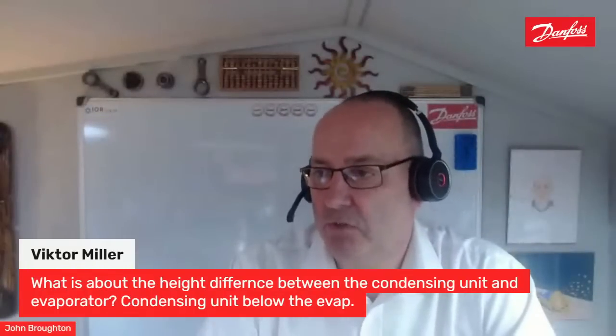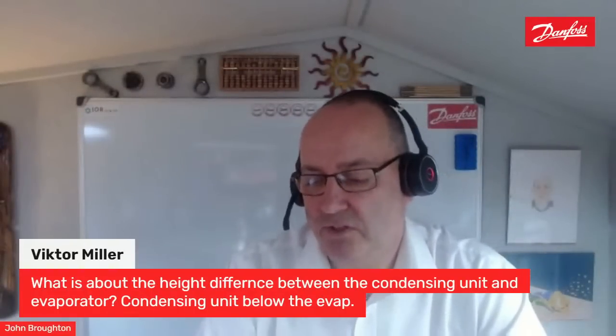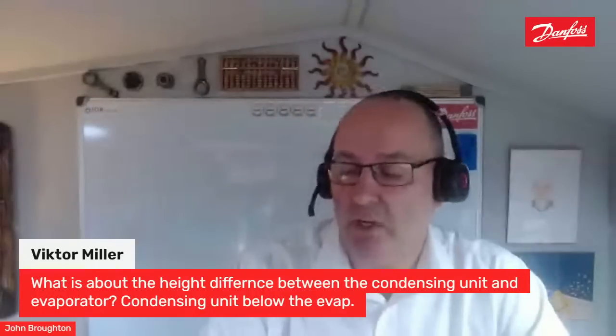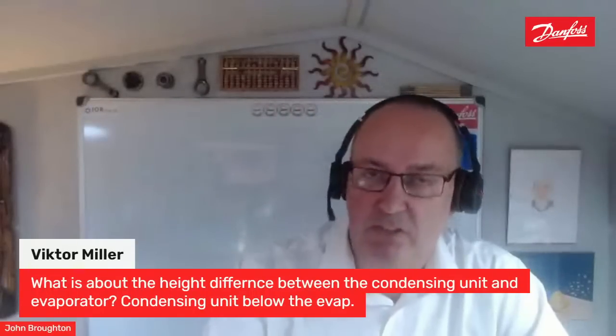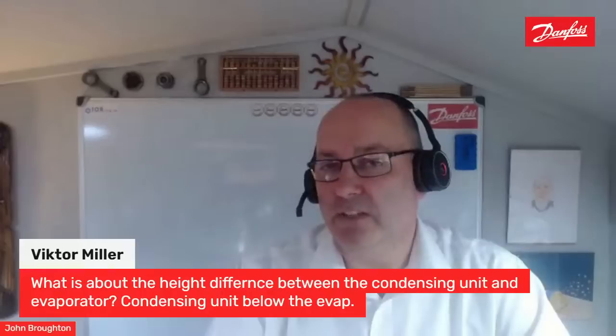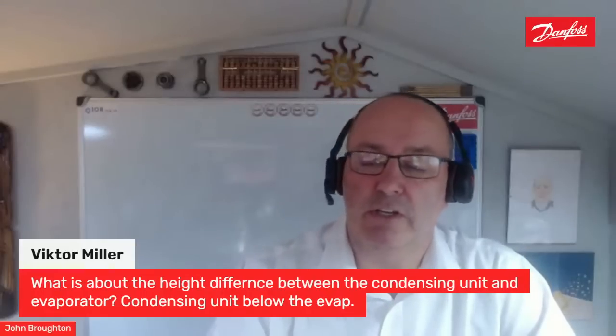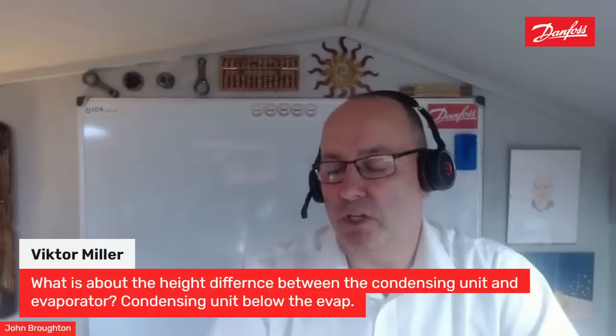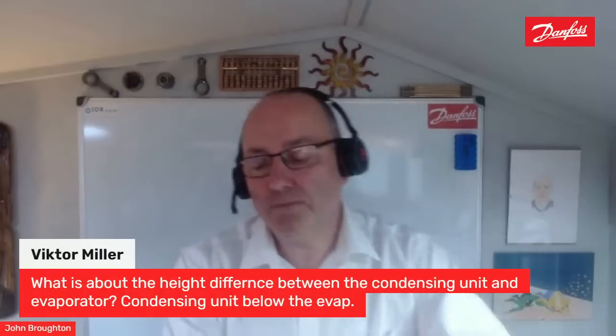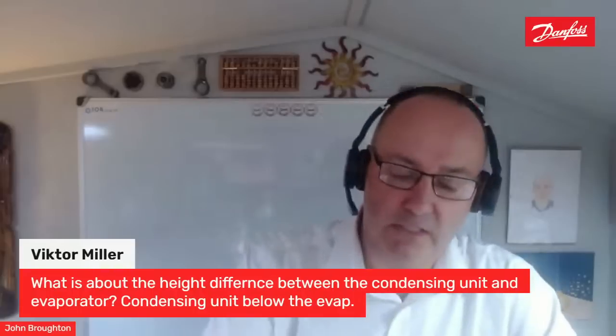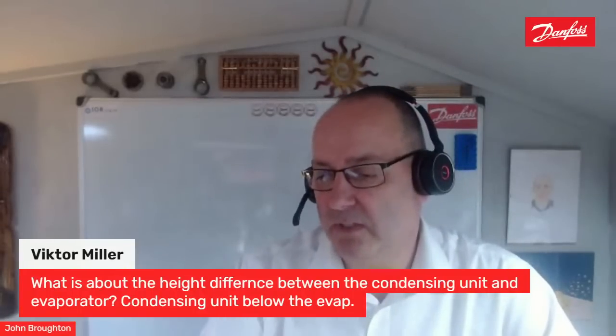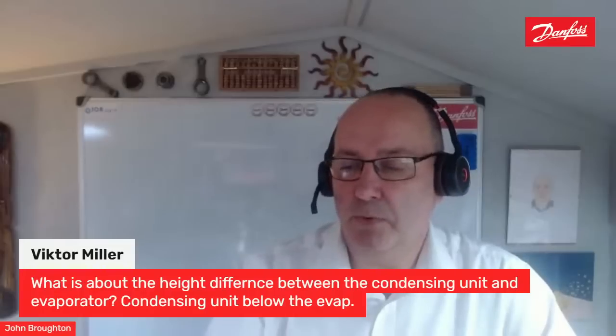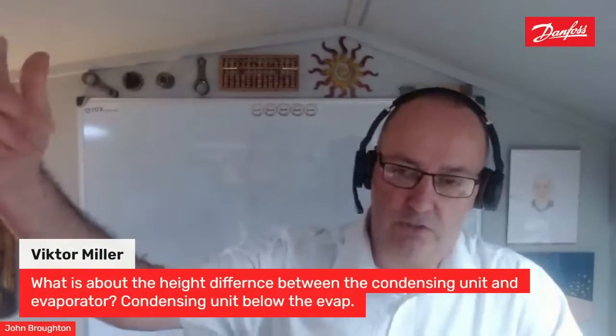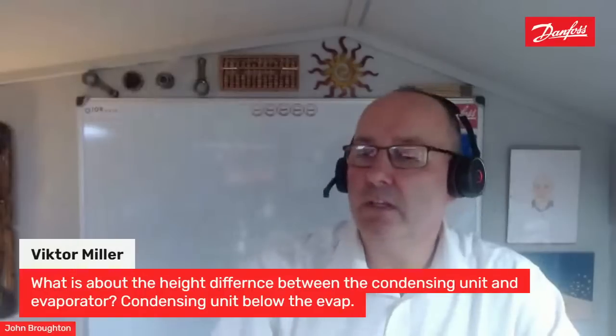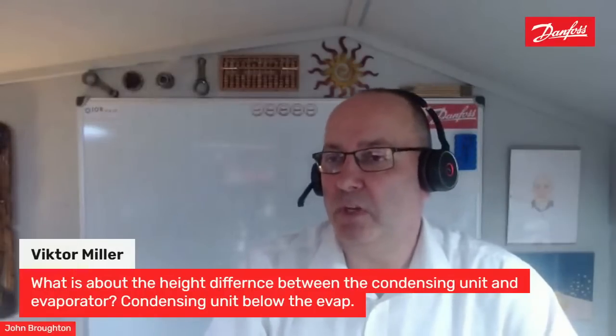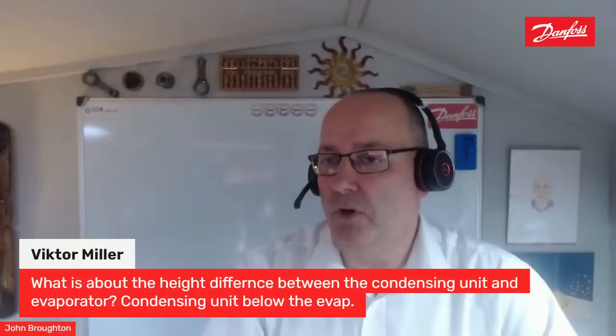Obviously, we've got to maintain the correct velocity, both in the liquid line and the suction line. Coming back to this point that I always labour, if we get the velocity right in the suction line, then we will get oil back to our machine. If the pipes are going vertical and the evaporator is above the condensing unit with the suction line coming back, then the oil is going to flow. If the condensing unit is above the evaporator, then we need oil traps in that suction line riser.